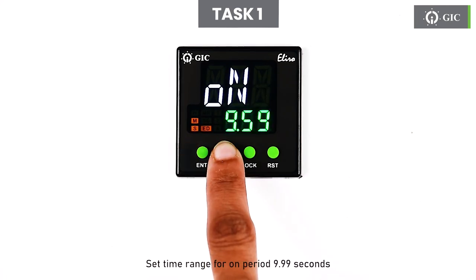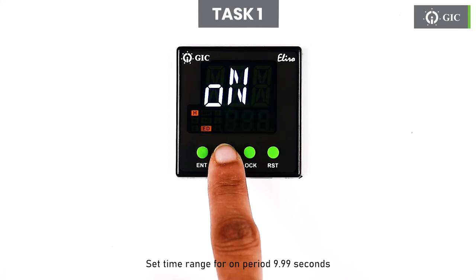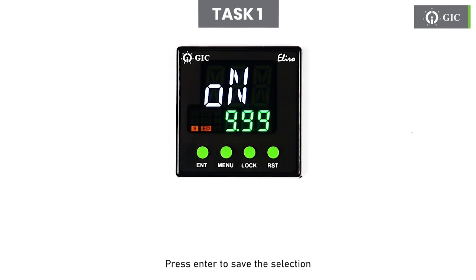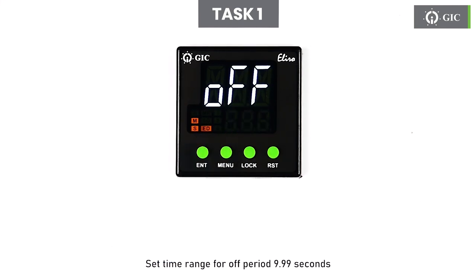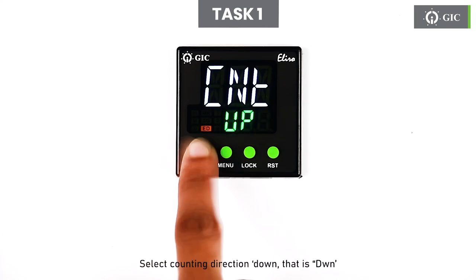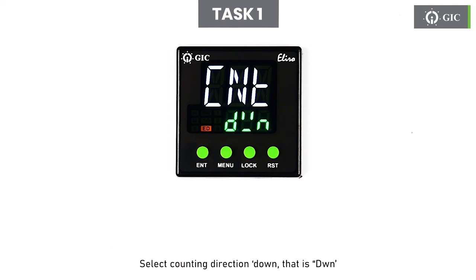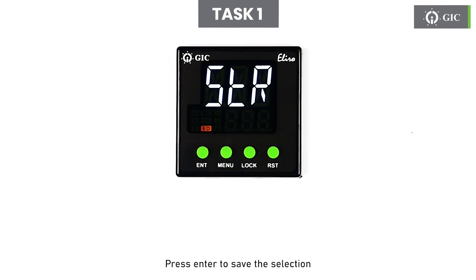Set time range for on period, 9.99 seconds. Press Enter to save the selection. Set time range for off period, 9.99 seconds. Select counting direction down, that is DWN. Press Enter to save the selection. Select input pulse. Press Enter to save the selection.